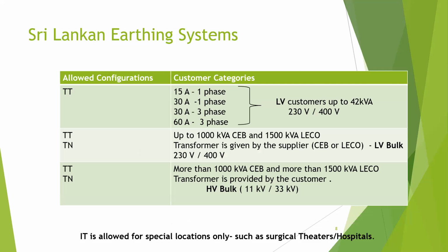Now, earlier I said that TT is only for domestic customers. Domestic customers are also called LV customers. So LV customers should have the TT earthing system installed in their house. Domestic customers can be categorized as customers with a demand lower than 42 kVA. Usually you have seen houses with single phase 15 ampere connections, single phase 30 ampere connections.